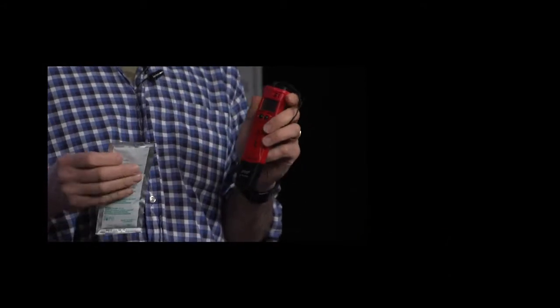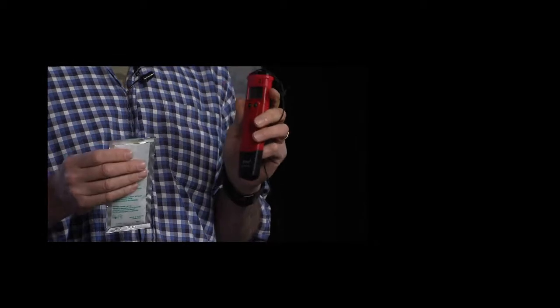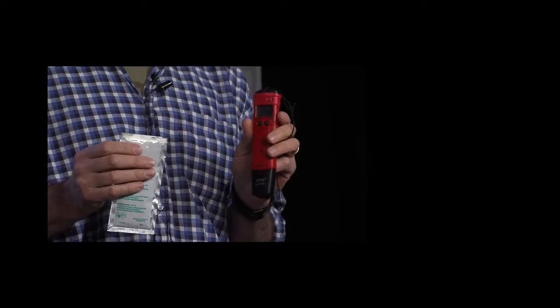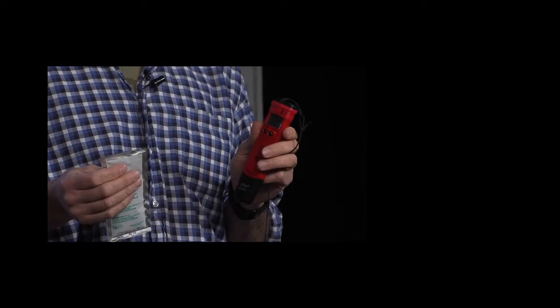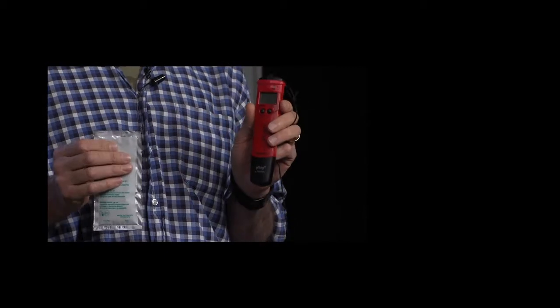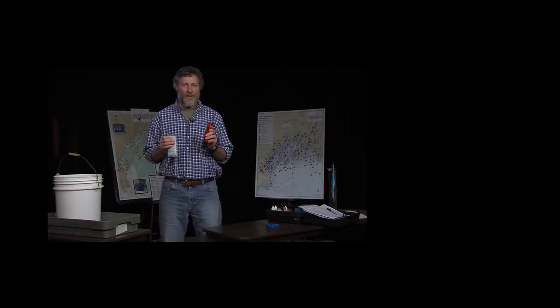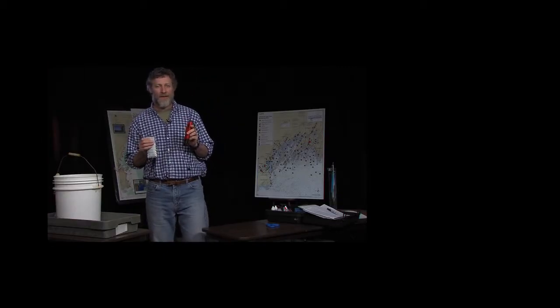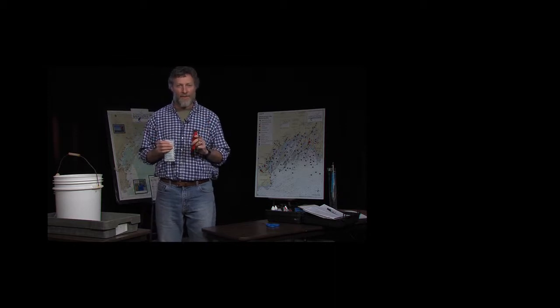We're going to talk today a little bit about calibrating the pH meter. This is a Hanna pH meter that we use at Friends of Casco Bay, and I'm going to talk a little bit about that because we like to calibrate these meters before every time we use it, so that we know that when we go into the field, they're going to be accurate, they're going to give us an accurate measurement, and we can justify that the data that we collect with these are going to be credible.